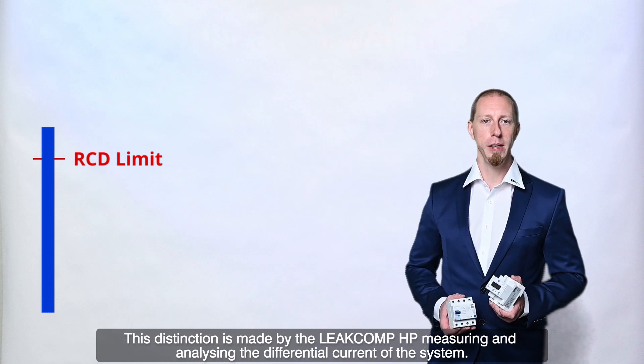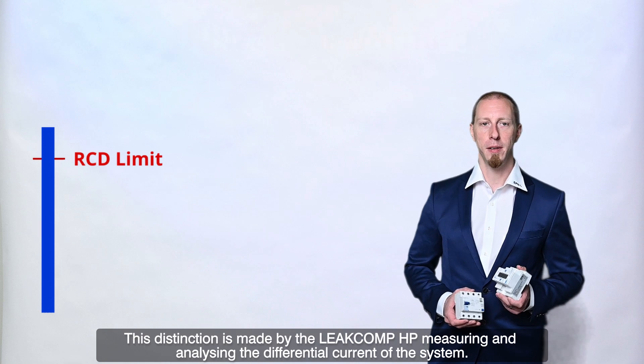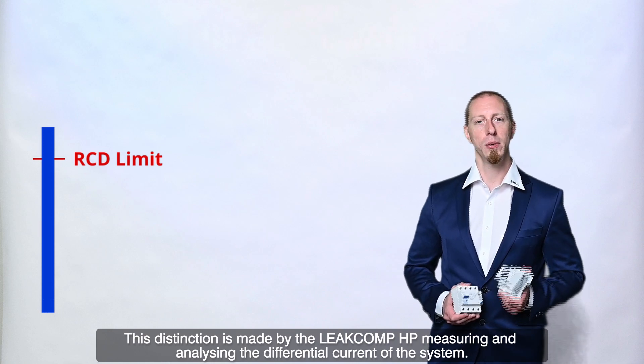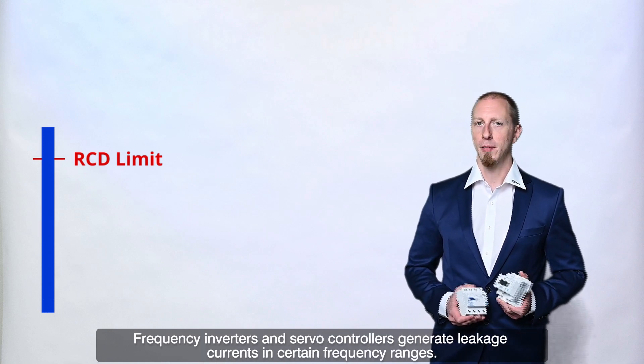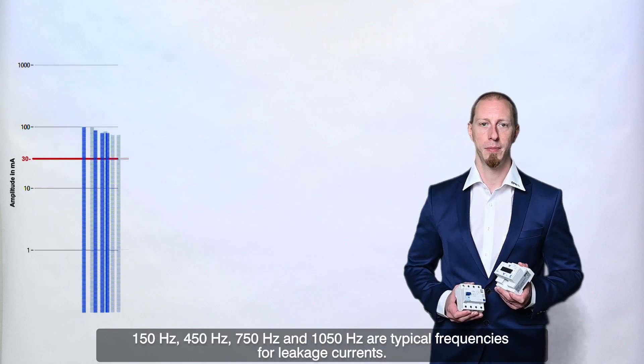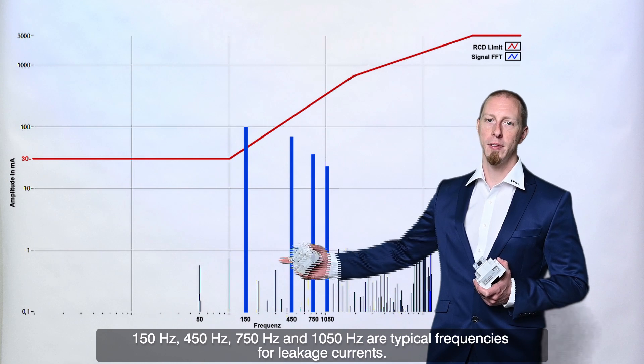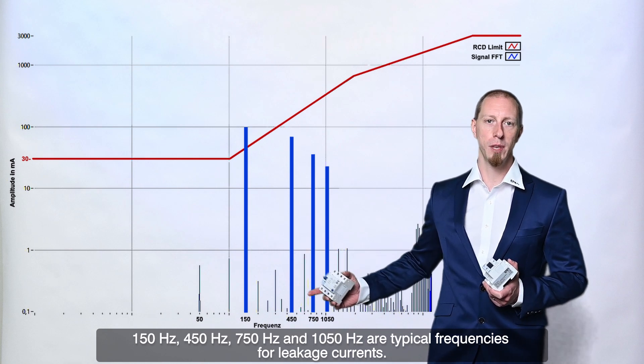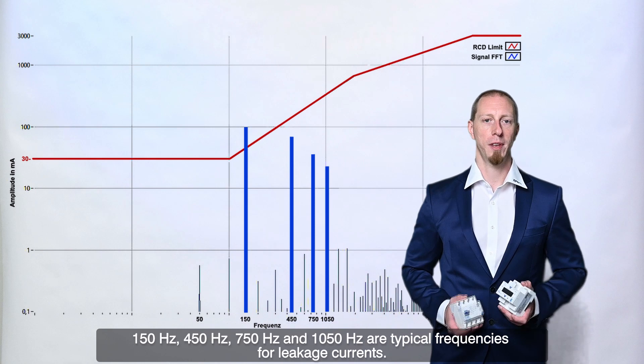This distinction is made by the Leakcomp HP measuring and analyzing the differential current of the system. Frequency inverters and servo controllers generate leakage currents in certain frequency ranges. 150 Hz, 450 Hz, 750 Hz and 1050 Hz are typical frequencies for leakage currents.